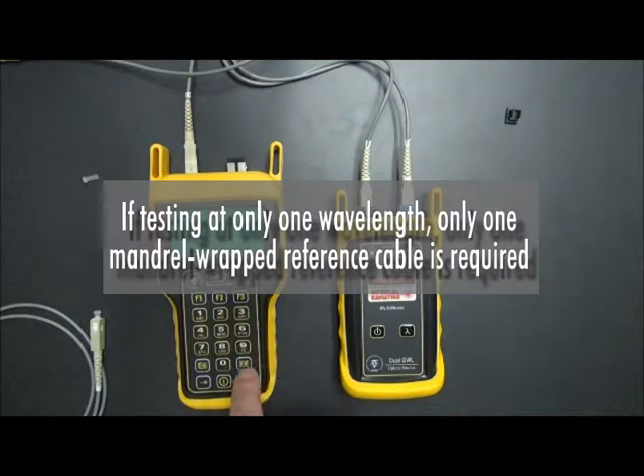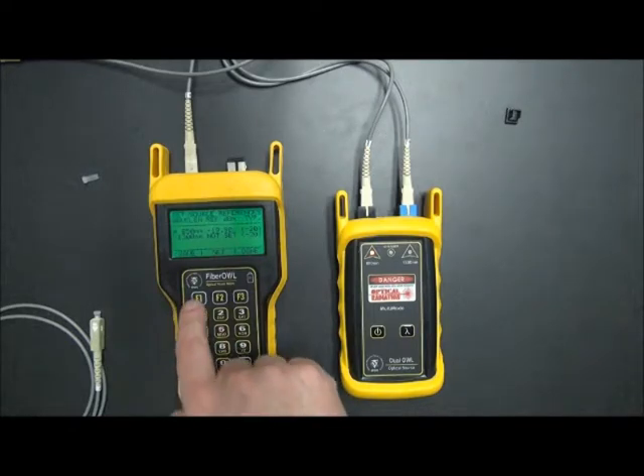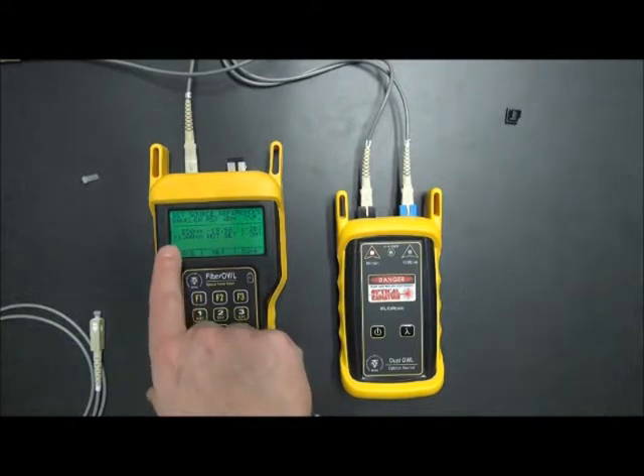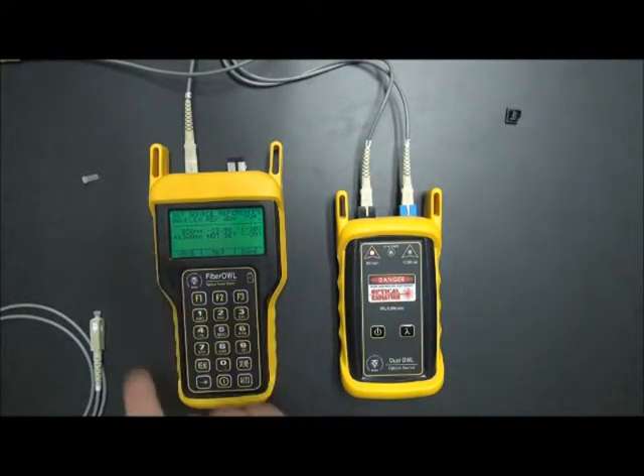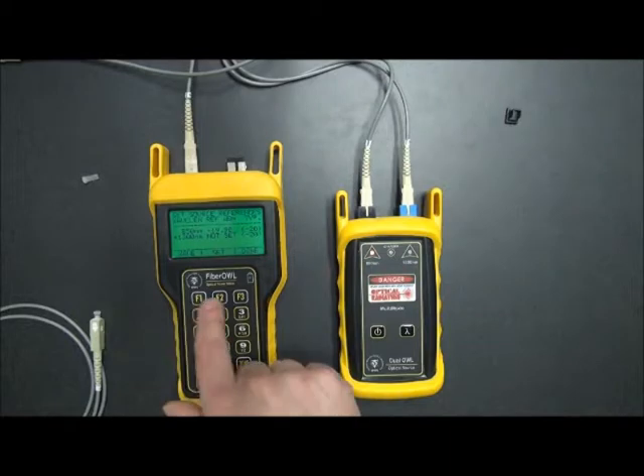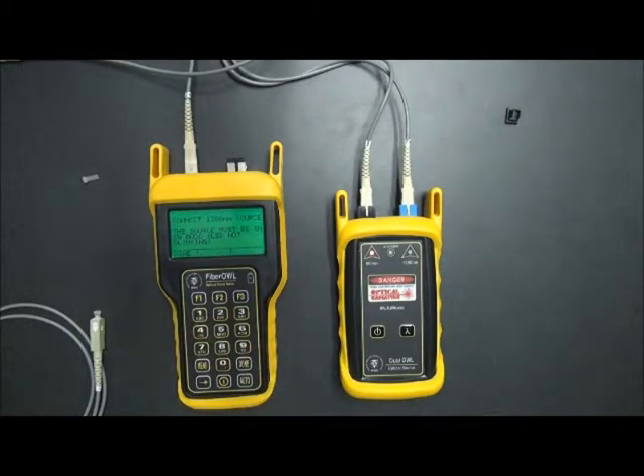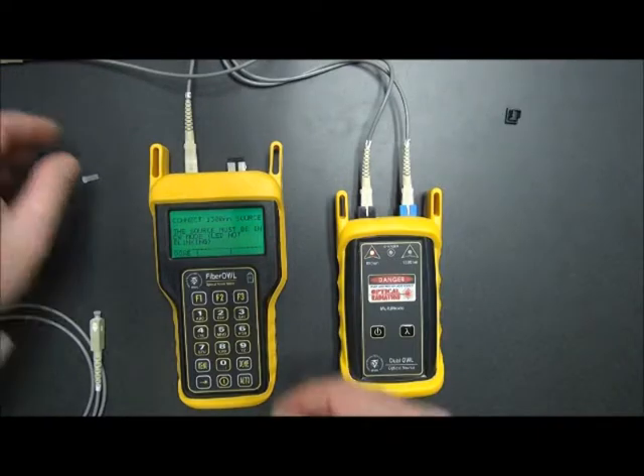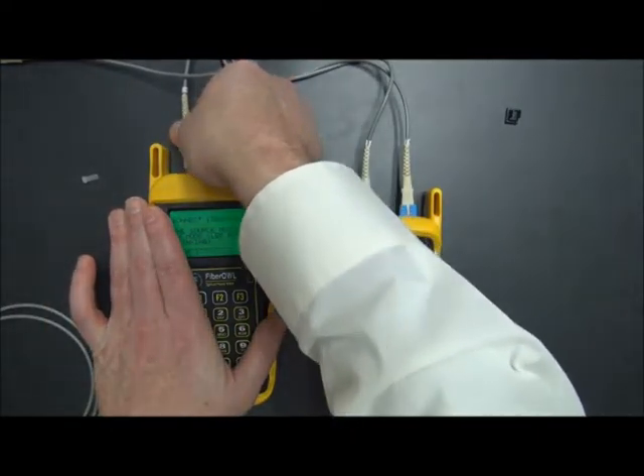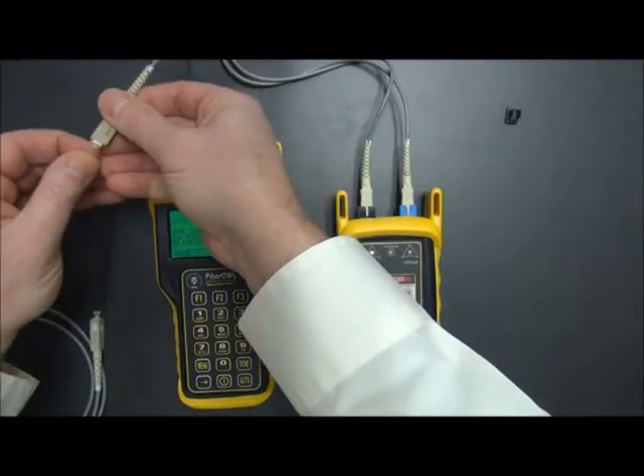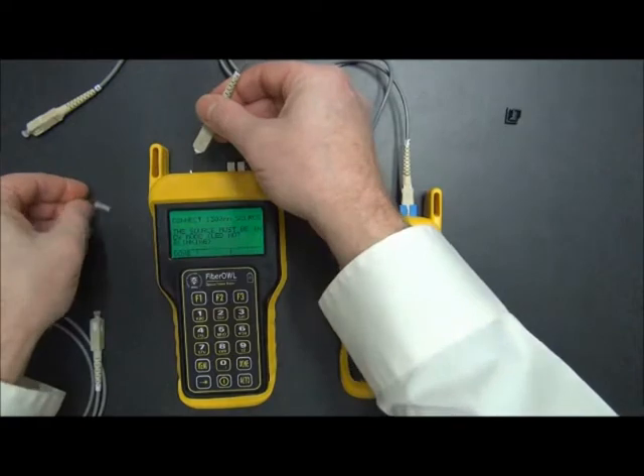If you do want to store at 1 wavelength, you can do that, and you would simply press done. However, since we do want to test both wavelengths, we're going to press F1 to switch the wavelength. Now the asterisk is in front of 1300. And then we simply hit set again. But now it's saying connect the 1300 nanometer source. So what we have to do is disconnect from the power meter. Take the 1300 nanometer reference cable and plug it into the detector port.